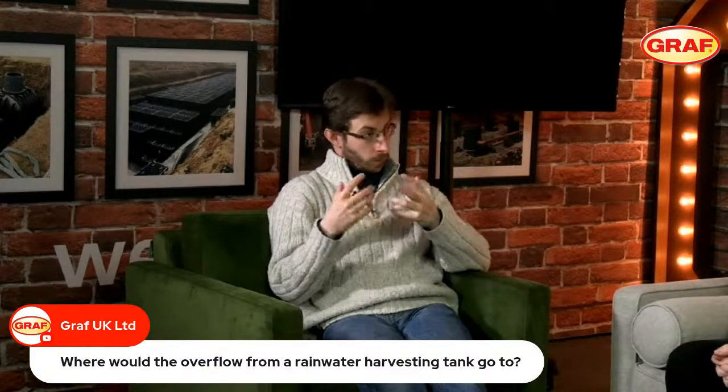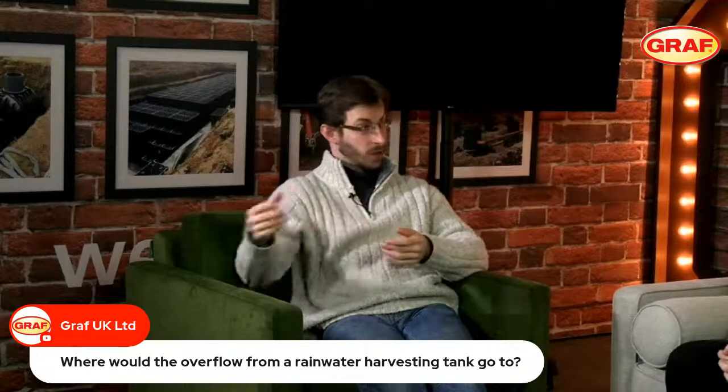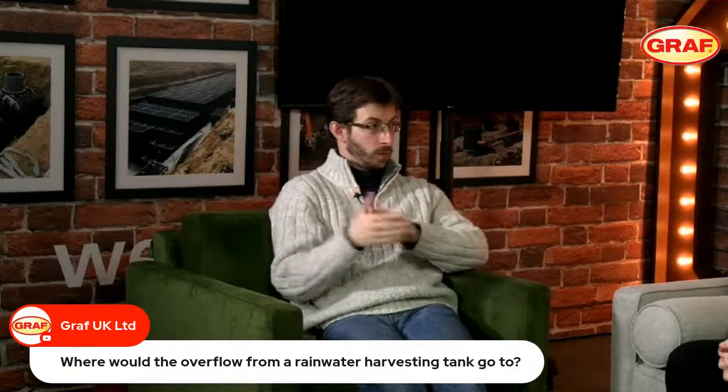It might be that if the ground conditions are very poor, we might need to discharge that to a storm drain. There may be other options available on the site, but those would be the primary two we would look at. Certainly when we talk about Graf systems, we offer certain filters depending on the type of solution you're going to be discharging to. If we're going to a soakaway, we'd normally look at some sort of basket filter, so all the leaves and debris are retained within the filter. If we're going to a storm drain or potentially another option, we would look at one of our self-cleaning filters where the water is washed over the top of the filter and all the leaves and debris would escape down the pipeline after the tank, which we wouldn't want in our soakaway.